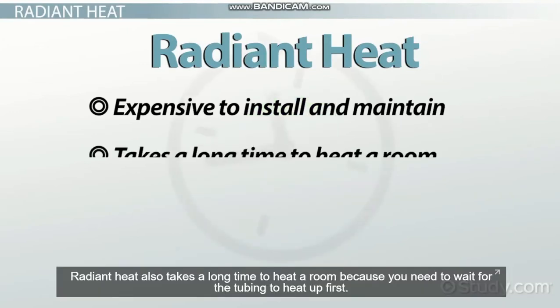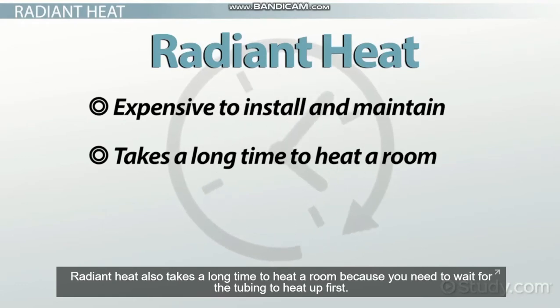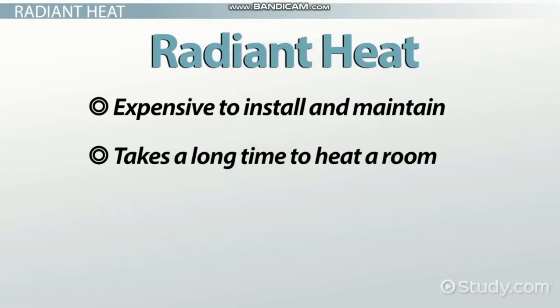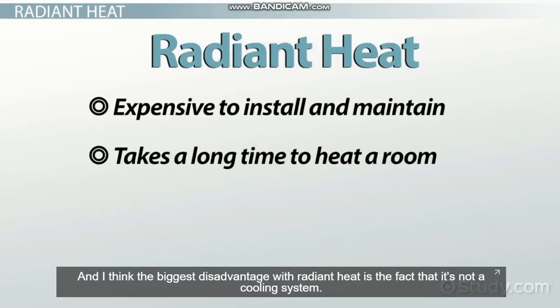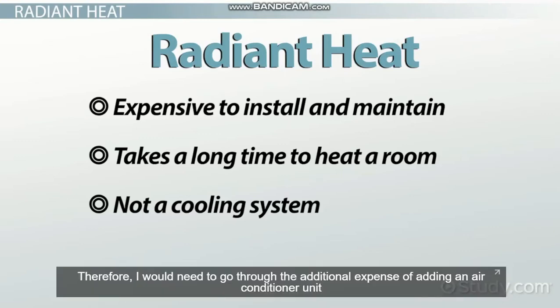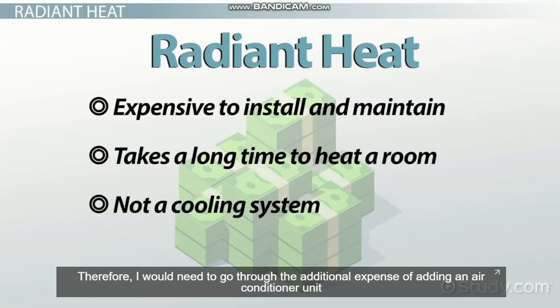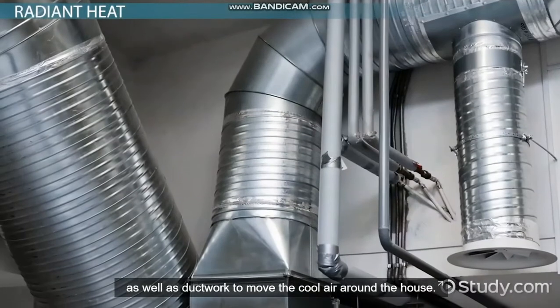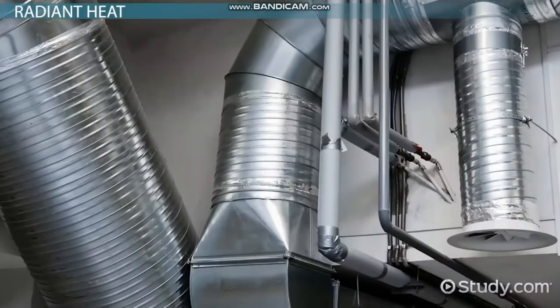Radiant heat also takes a long time to heat a room because you need to wait for the tubing to heat up first. And I think the biggest disadvantage with radiant heat is the fact that it's not a cooling system. Therefore, I would need to go through the additional expense of adding an air conditioner unit as well as ductwork to move the cool air around the house.